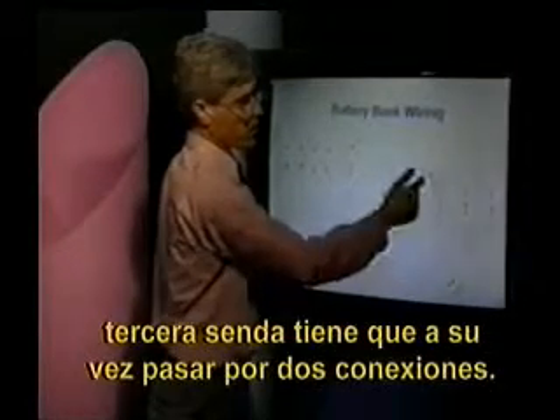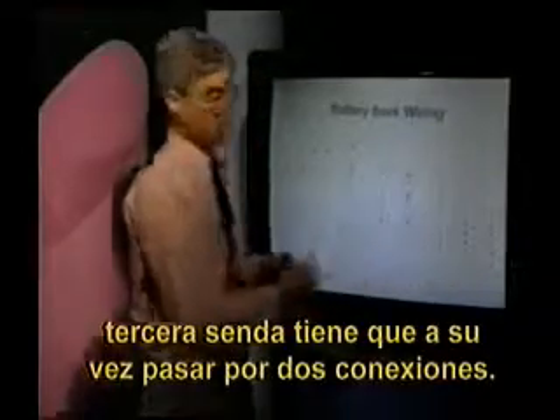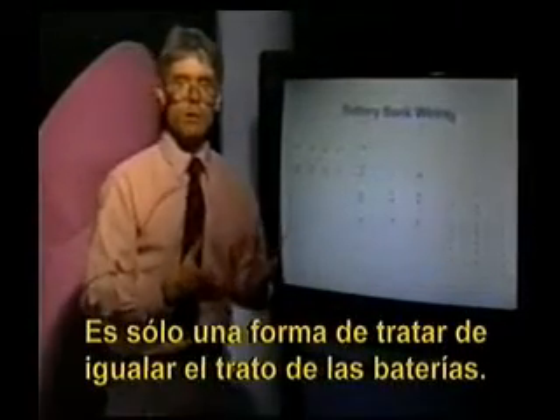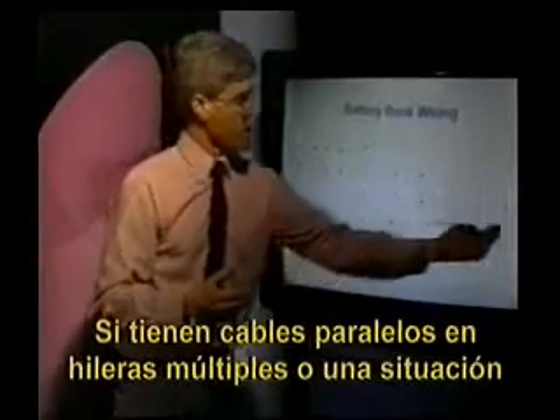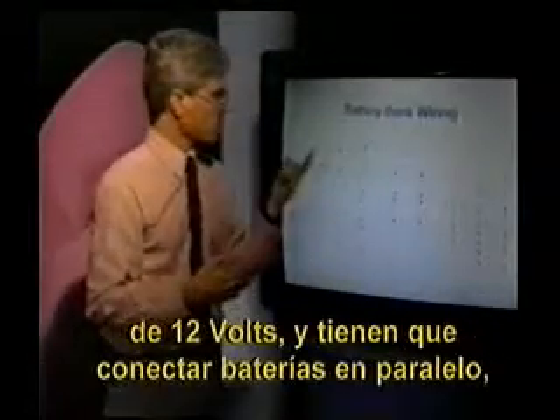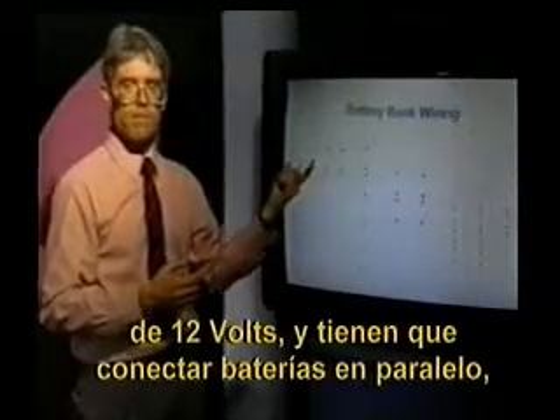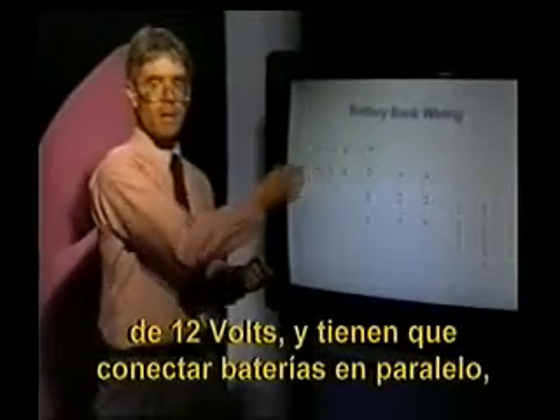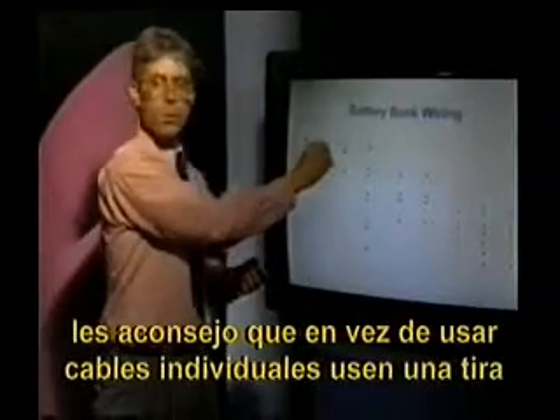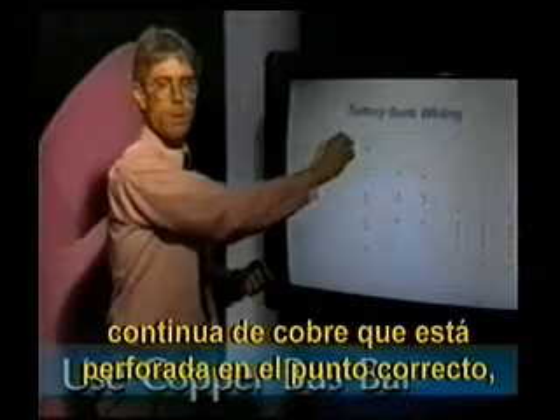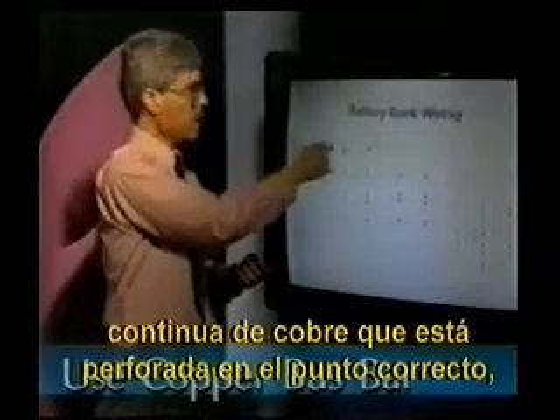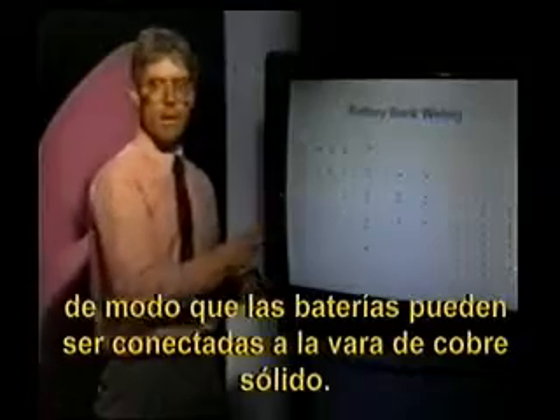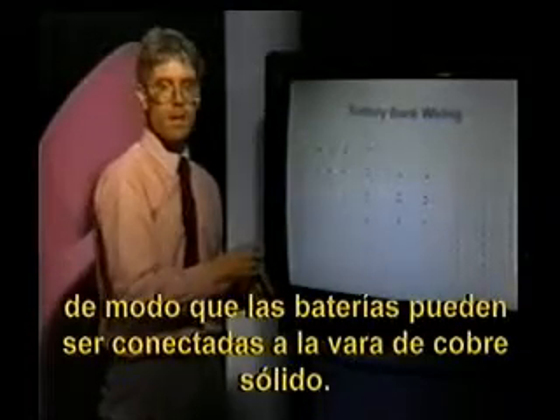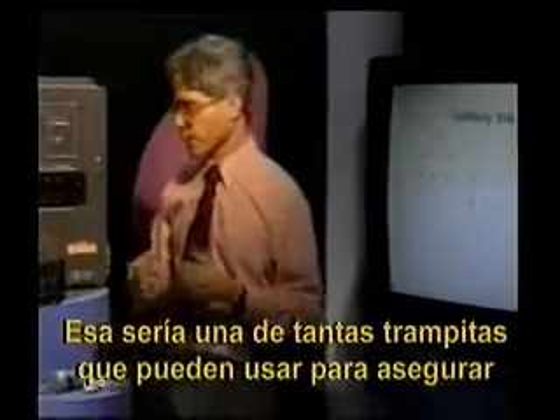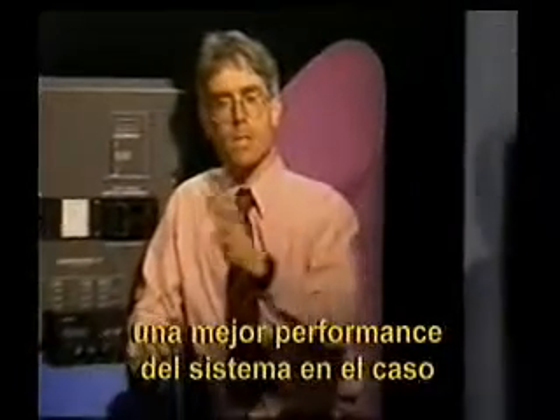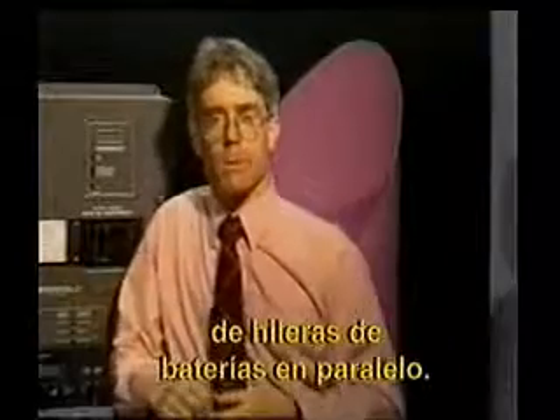And to flow through the third path, it has to go through 2 connections as well. Just a way to try and equalize the treatment of your batteries. If you have a situation of parallel wiring, either multiple strings or like we talked about in our 12-volt situation, and you have a number of batteries to connect in parallel, one advice is instead of using individual wires, to use a continuous strip of copper that's drilled at the right point so that the connecting lugs of the batteries can be connected to the solid copper rod. That would be one of many tricks that you could use to ensure a better system performance in the case of parallel battery strings.